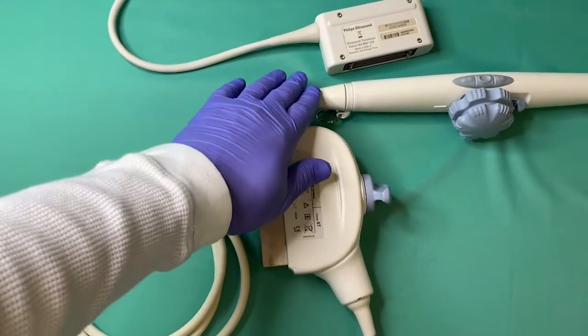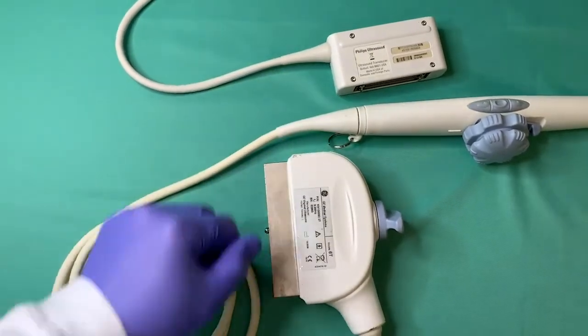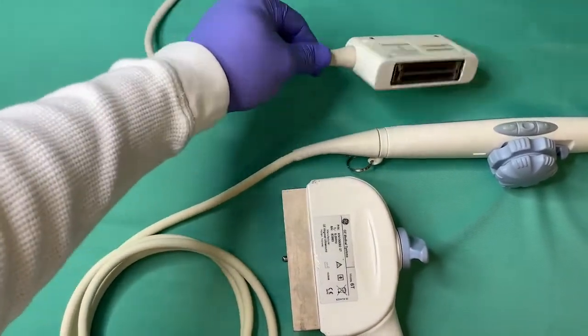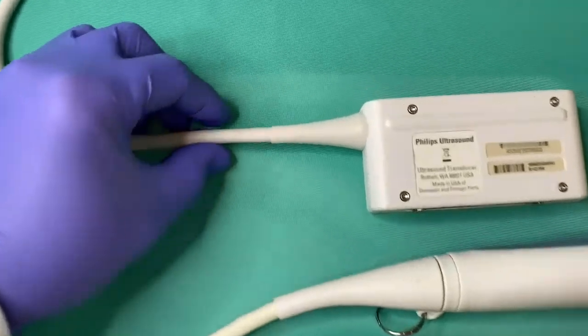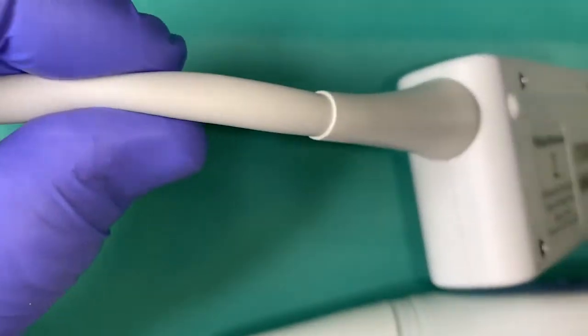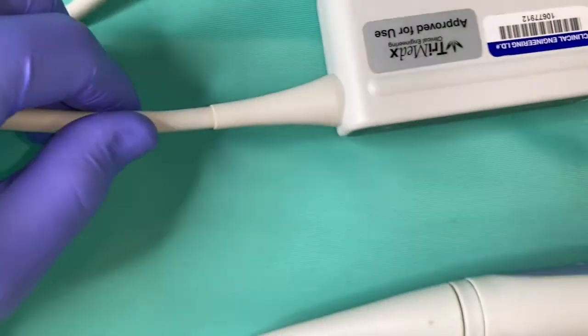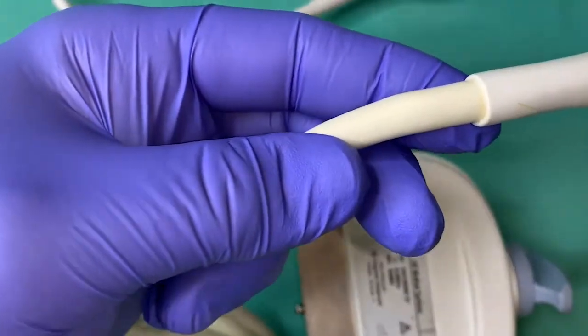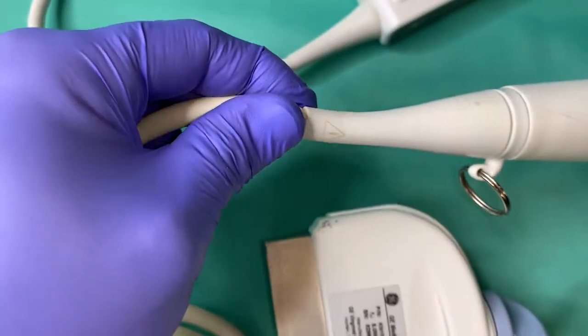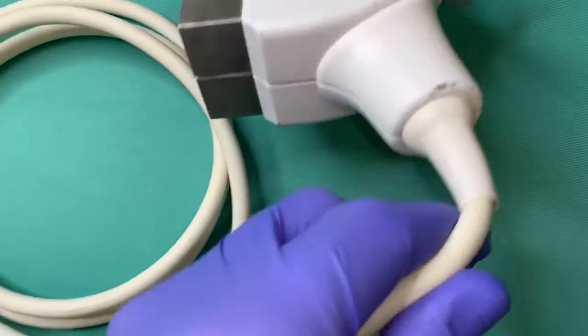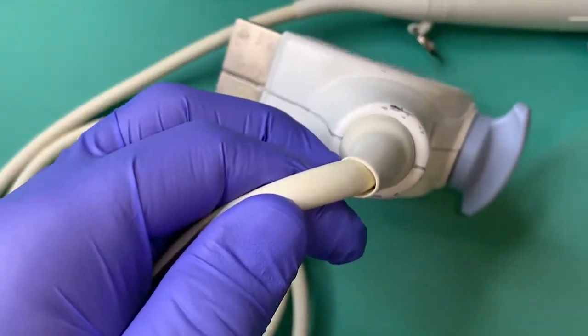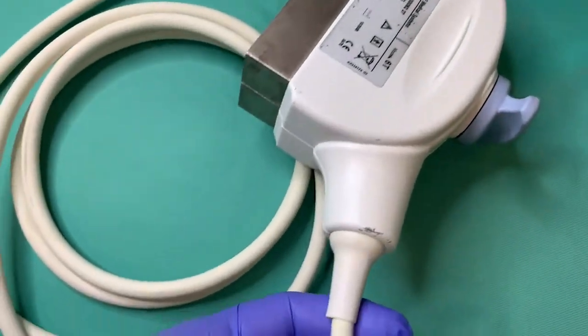Strain reliefs are located at either end of the system cable, and they should be very flexible. The strain relief itself may or may not be sealed to the cable sheathing, based on the specific OEM design. Inspect each strain relief for any cuts, tears, or any other kind of mechanical damage.